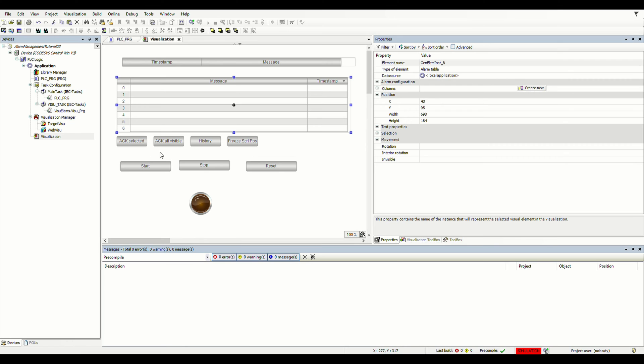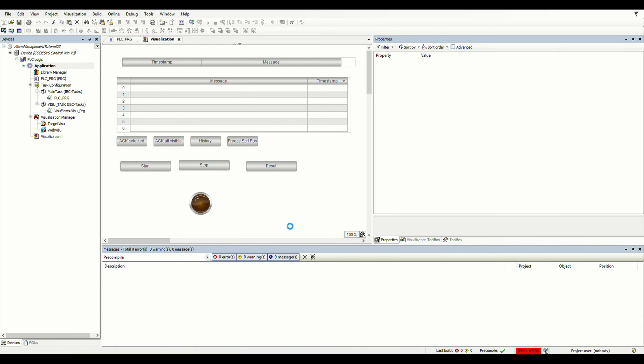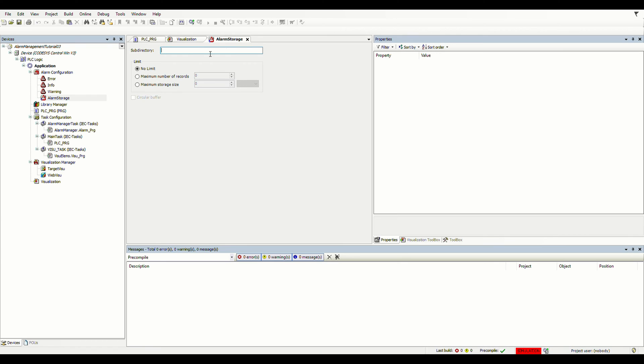We can also introduce controlling buttons for the alarm table — I'll explain their functionalities later. To add alarms to our system, right-click on the application and choose Add Object, then Alarm Management — Alarm Configuration. When we have the alarm configuration open, we have a couple of elements already there: error, info, and warning are three different classes of alarm. You can use them in your project or create new ones. We also have the alarm storage, which is used to store alarm conditions.